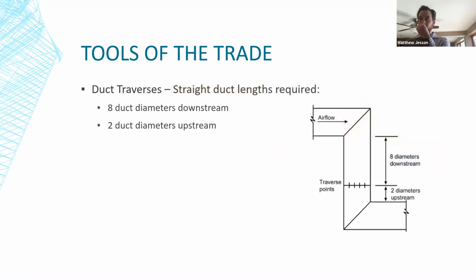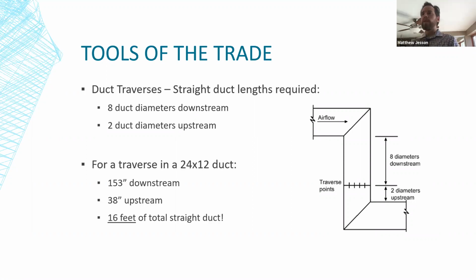So what does that mean? What do you really need for a good duct traverse? So this is a diagram of an ideal duct traverse location. You need, downstream from an elbow or a change in size, a takeoff, anything that interrupts flow or changes it, 8 duct diameters downstream, and then another 2 duct diameters upstream of another interruption. And so if you're talking rectangular duct, then you need to do a little math to convert to an equivalent diameter. But to make the math simple, for a traverse in a 24 by 12 duct, you need 153 inches downstream of an elbow and 38 inches upstream of one. That's about 16 feet total.